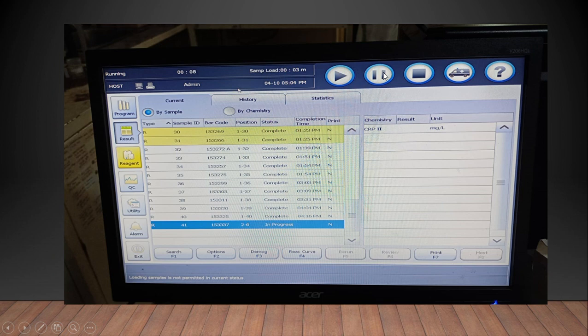The moment you click on the pause button, it will take some seconds and it will tell you at what time you can actually load the samples. For example, it is telling that after 3 minutes you can give samples to the instrument. Even though the test is still running, it will give you an option of loading. Remember, this is very different from the C311 instrument which we normally use. The C311 has a separate reagent probe, which is inside, a separate sample probe, and one more ISE probe also. So it has 3 probes and then a wash station.